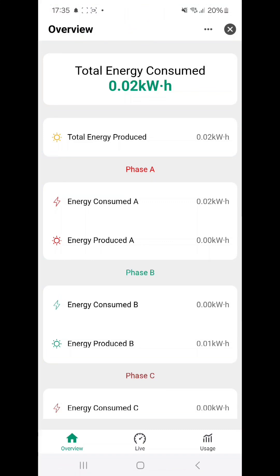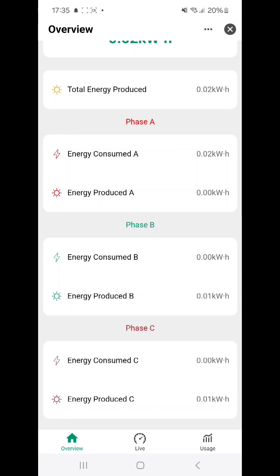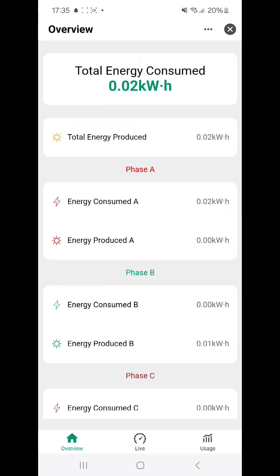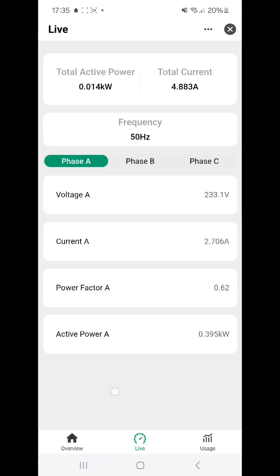Now that it is updated, we can see if something is being produced or consumed. It says the energy is at zero kilowatt hours. Looking at the live values, the total current being used is 5 amperes and only 0.01 kilowatt. Breaking it down: phase A has 2.8 amperes, phase B around 1 ampere, and phase C also around 1 ampere.